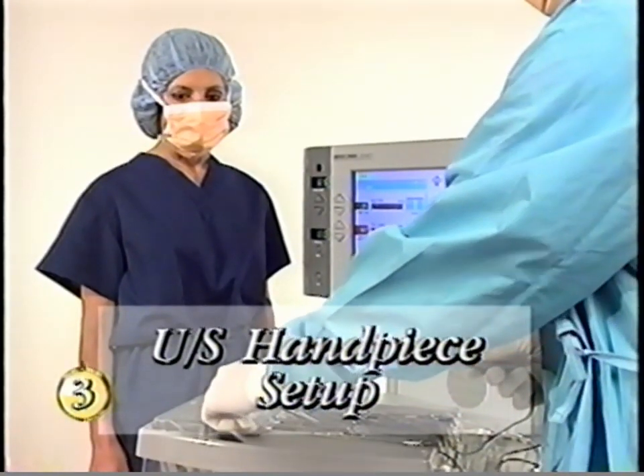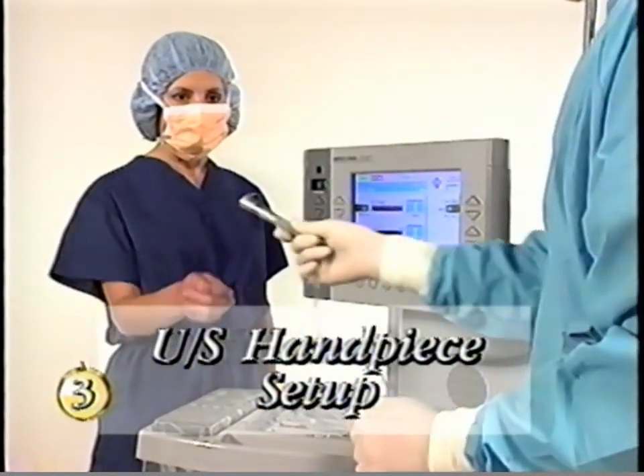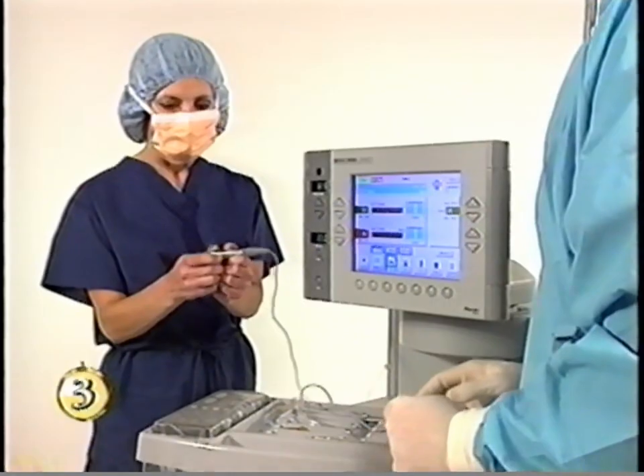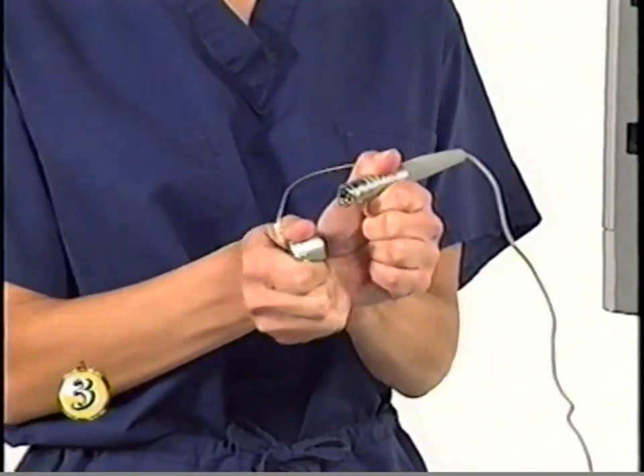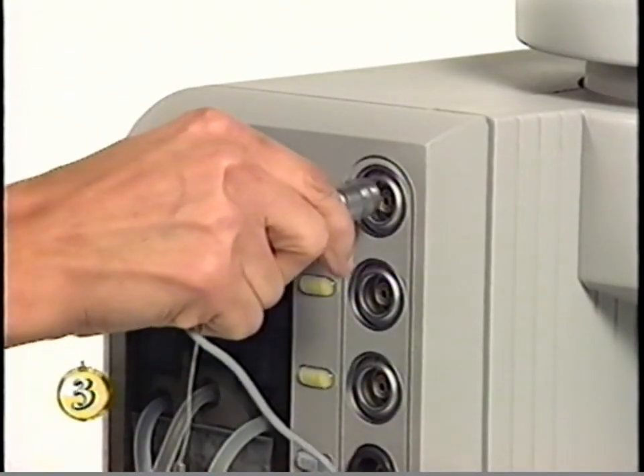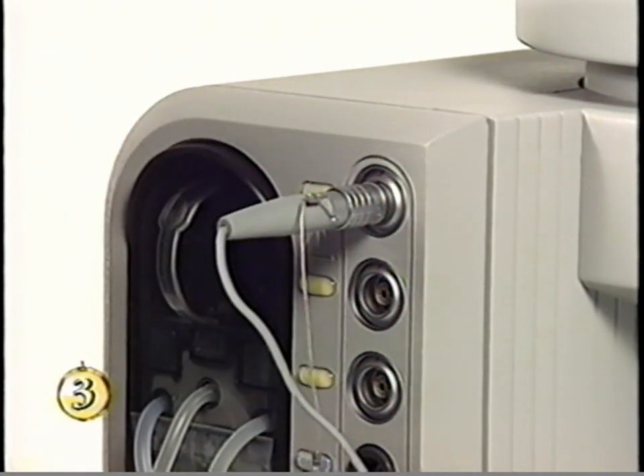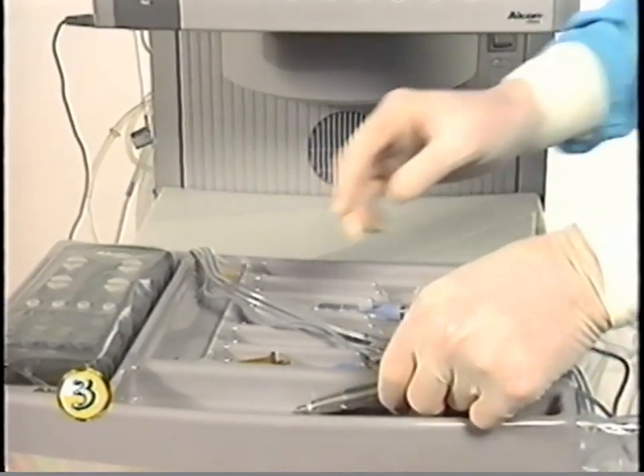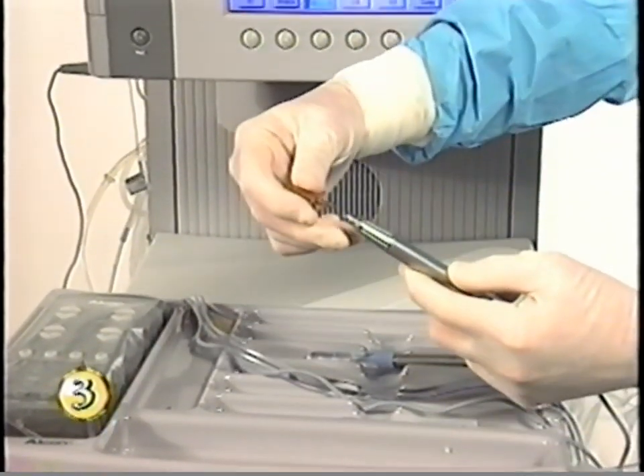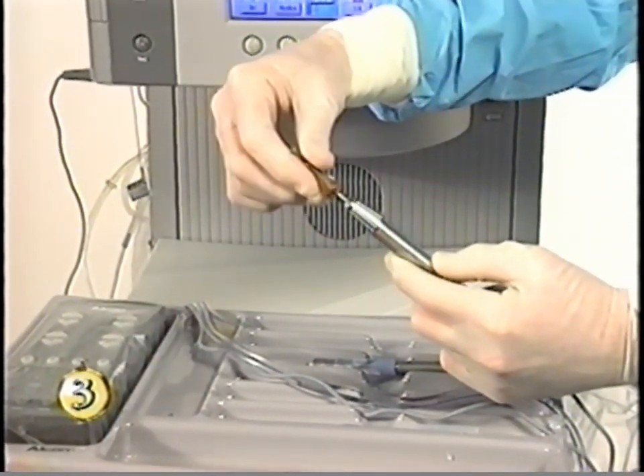To set up the ultrasound handpiece, select US mode. Remove the protective cap from the connector by retracting the connector sheath and releasing the cap. Connect it to any ultrasound connector socket on the left side panel. Thread the ultrasound tip onto the handpiece and tighten it firmly with the tip wrench.